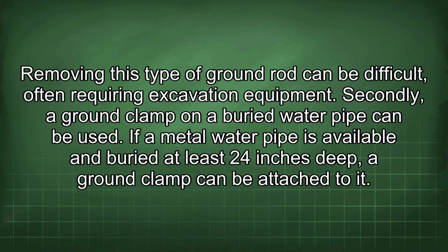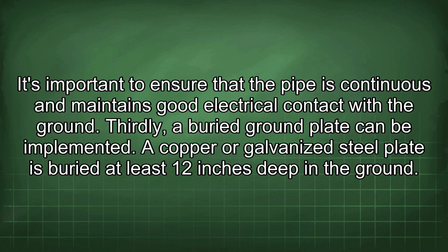Secondly, a ground clamp on a buried water pipe can be used. If a metal water pipe is available and buried at least 24 inches deep, a ground clamp can be attached to it. It's important to ensure that the pipe is continuous and maintains good electrical contact with the ground.